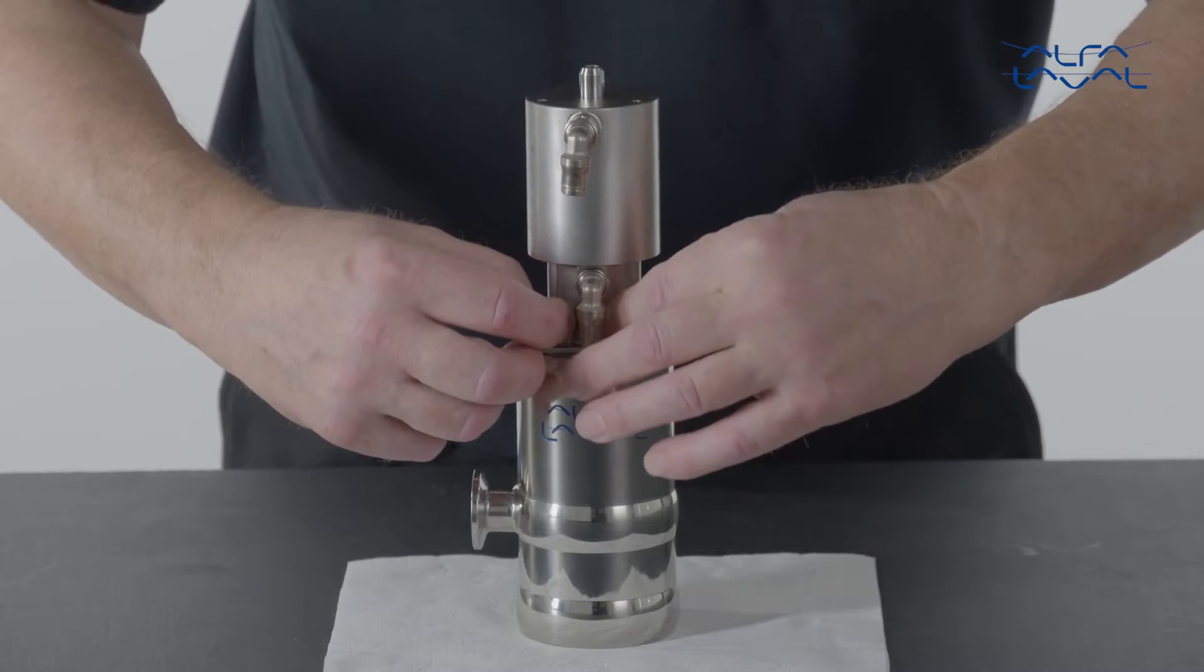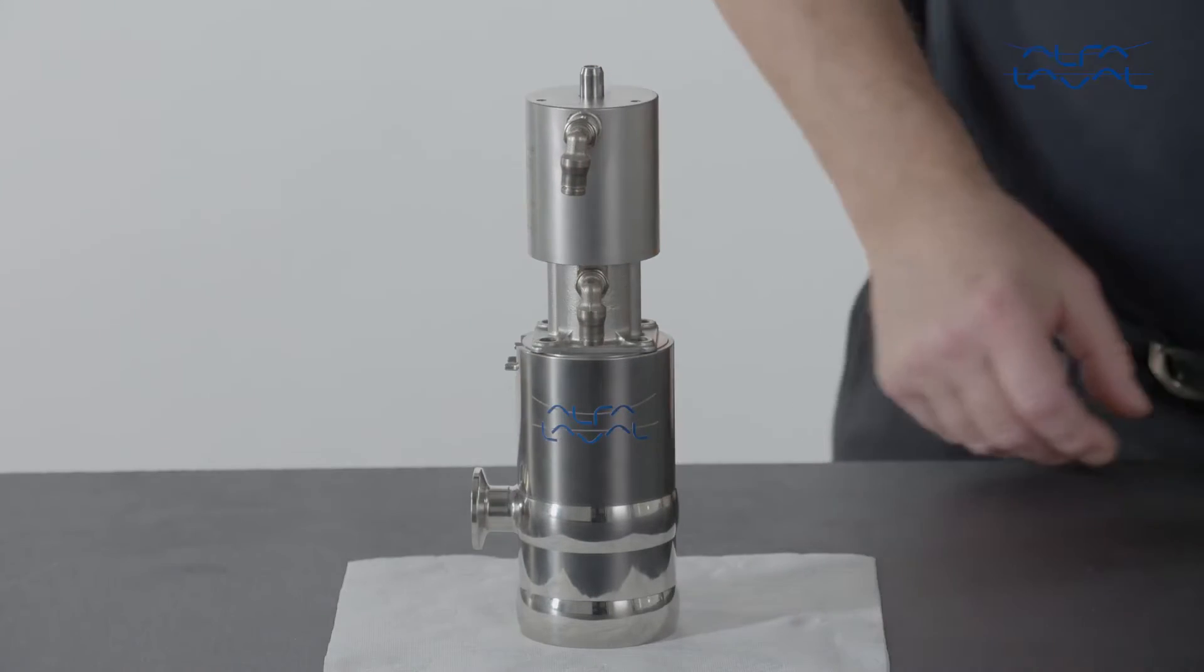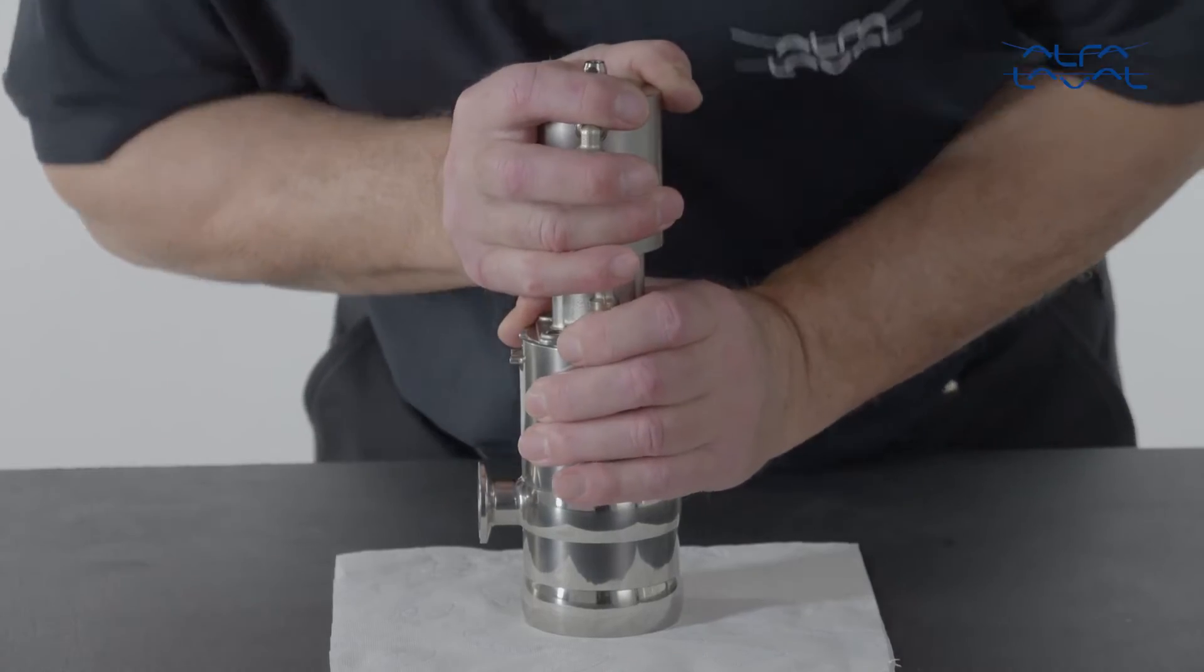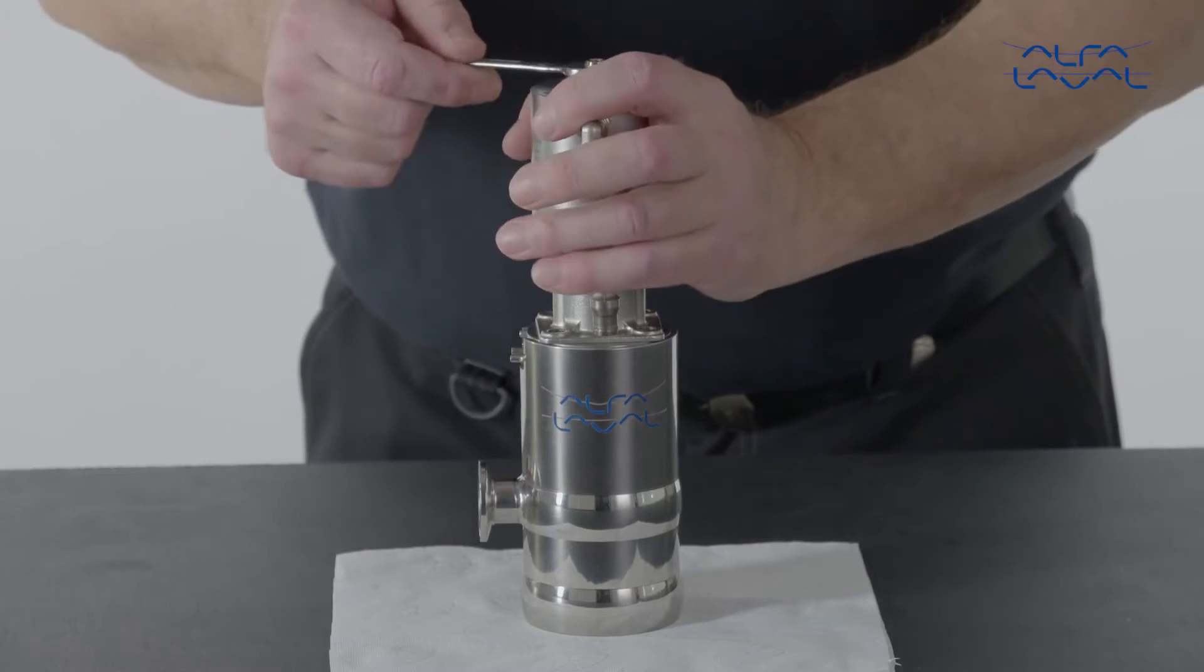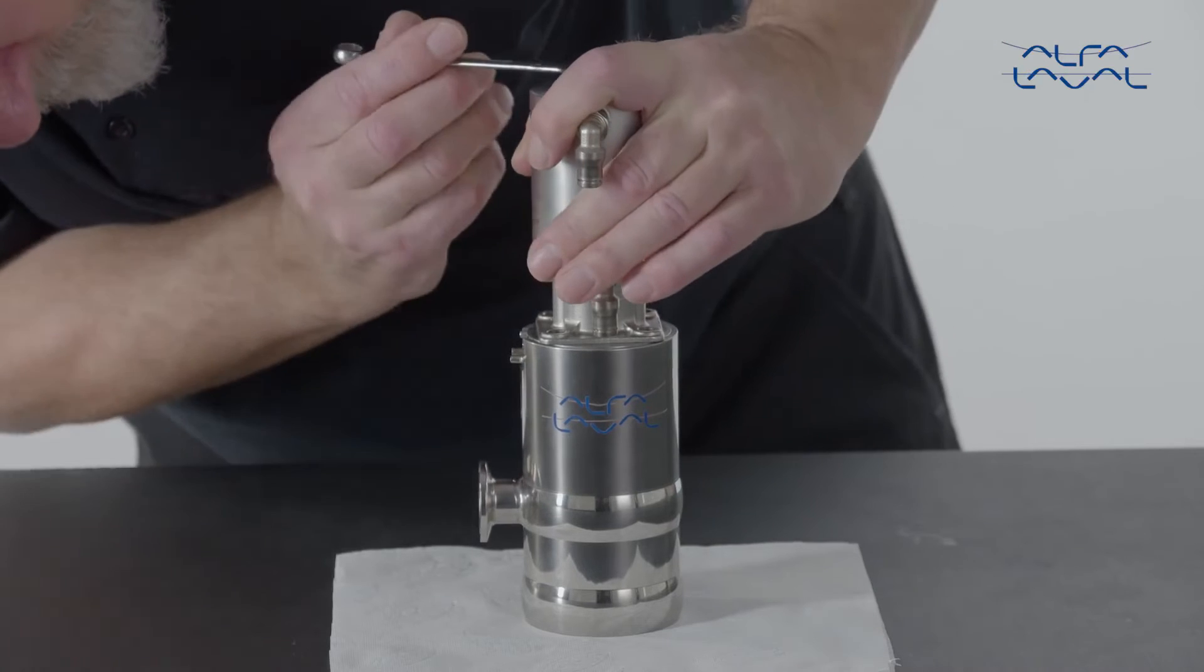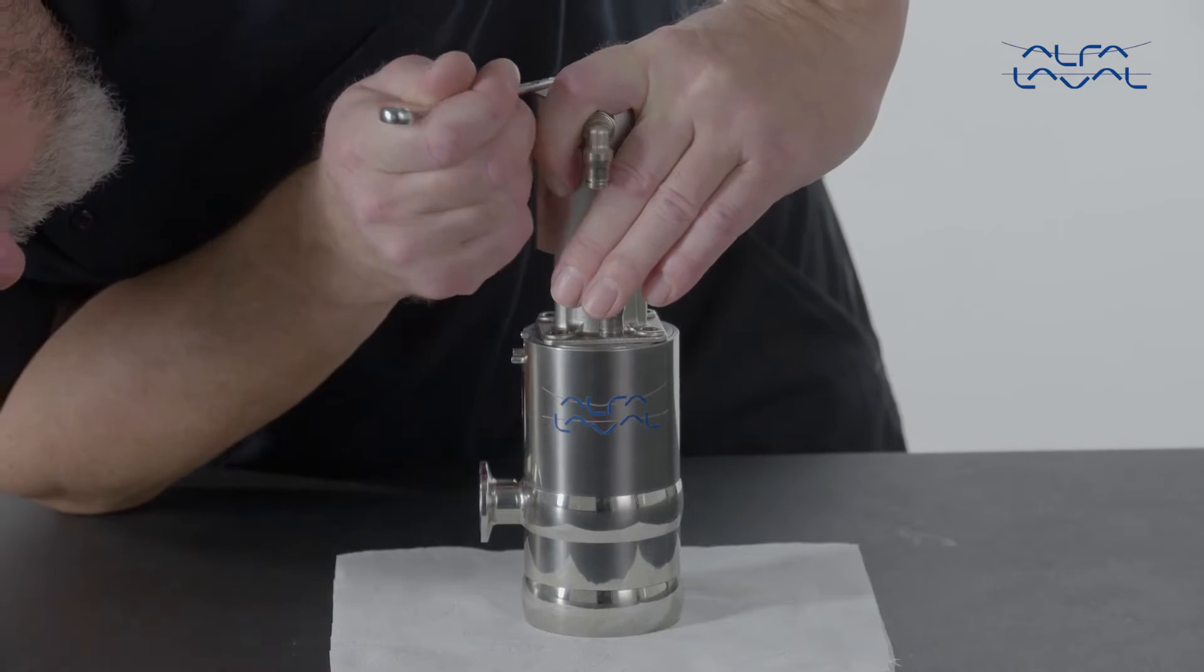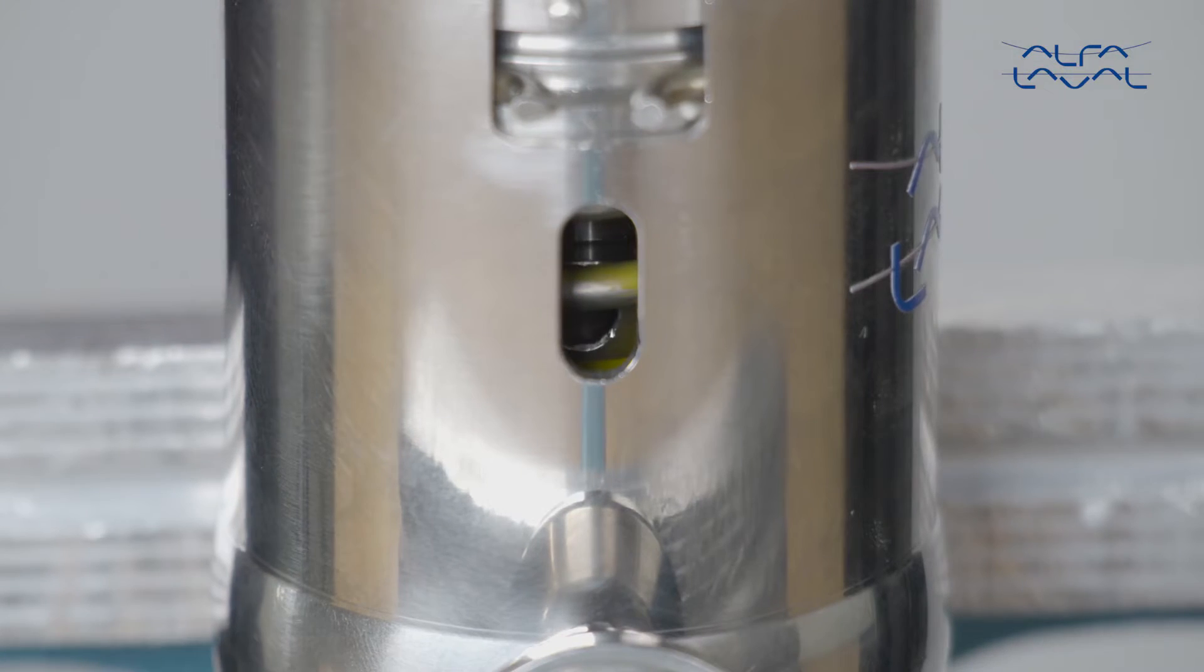First, remove the screws that hold the actuator in place. Now rotate the actuator piston counter-clockwise to demount it. In case the actuator sits too tight, use a wrench and rotate the actuator spindle until the hole on the piston is aligned with the opening.